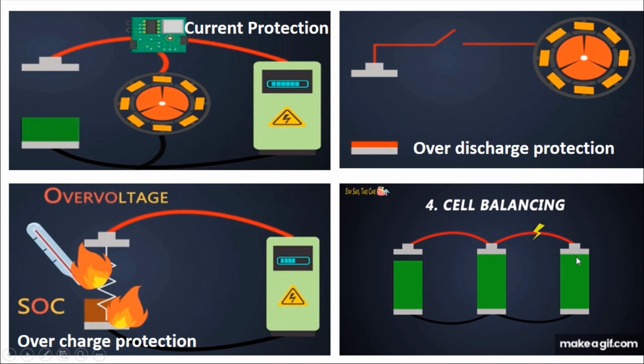What will happen is you will be discharging these batteries to 3.2 volt and down to 2.4 volt, and while charging you will charge it to 3.8 volt. So after certain cycles, you are going to damage the complete life cycle of these batteries and have to change them. Or else, the battery will overheat and damage your entire parallel connection of batteries. For example, in parallel you have 5 or 10 cells, so all of them will be damaged and you'll have to change the entire set.